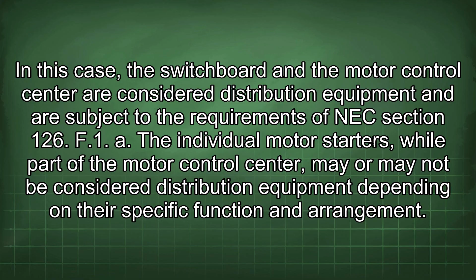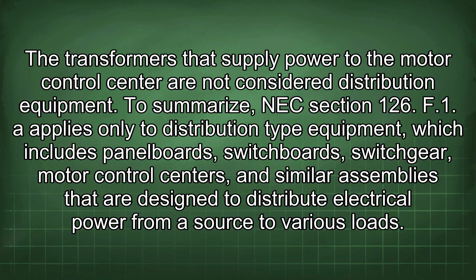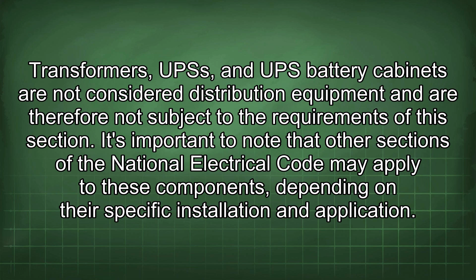126.F.1 applies only to distribution-type equipment, which includes panel boards, switchboards, switchgear, motor control centers, and similar assemblies that are designed to distribute electrical power from a source to various loads. Transformers, UPSs, and UPS battery cabinets are not considered distribution equipment and are therefore not subject to the requirements of this section. It's important to note that other sections of the National Electrical Code may apply to these components depending on the specific installation and application.